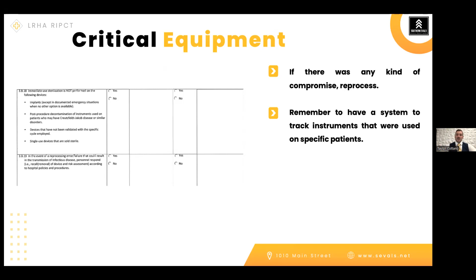Lastly, to wrap up our critical equipment, is there any kind of compromise? No matter what it is, is there a tear? Is it still wet on the inside? Is there a stain? Make sure that without a doubt, no matter what we do, just reprocess that item. Don't just leave it be. Make sure that you bring it back through the process and that everything checks out. And remember, make sure you have a system to track the different instruments used on the patients. Unfortunately, surgical site infections happen. And if we're going to do our root cause analysis, we need to understand if these instruments, maybe they had pitting, maybe they had rust, maybe they weren't processed properly. We have to have a system to track those things to recall what was used. So that's the big pieces from CMS.